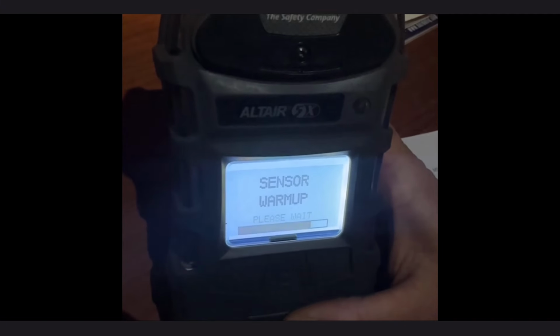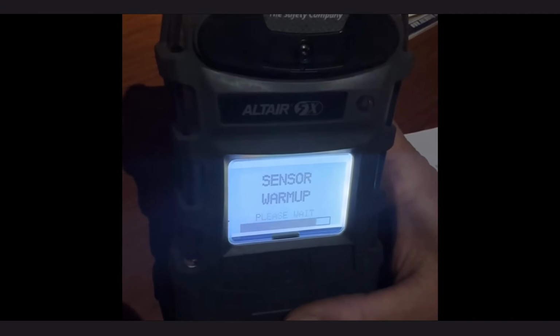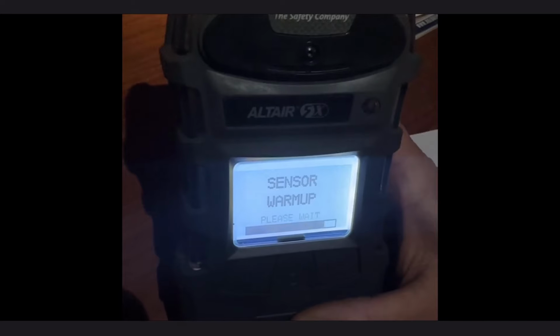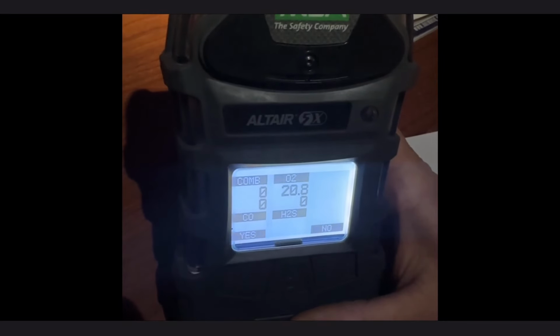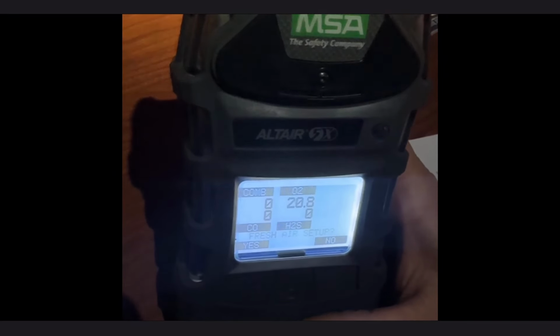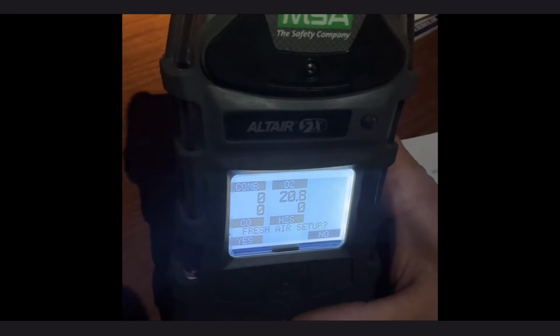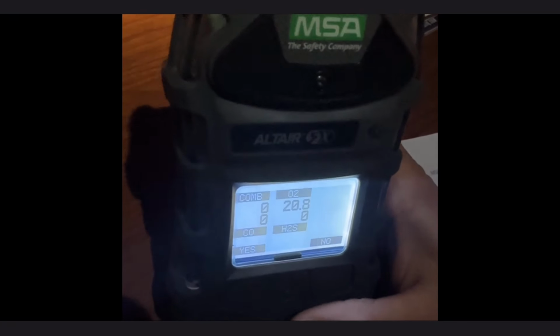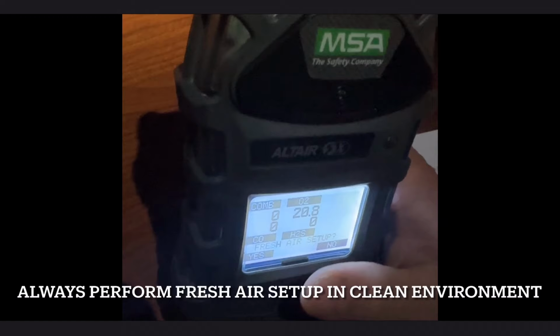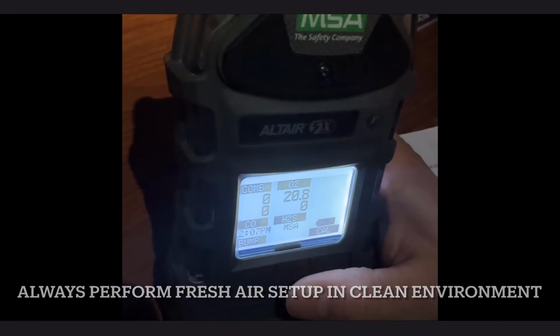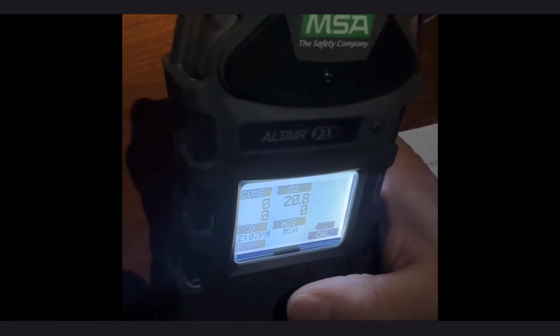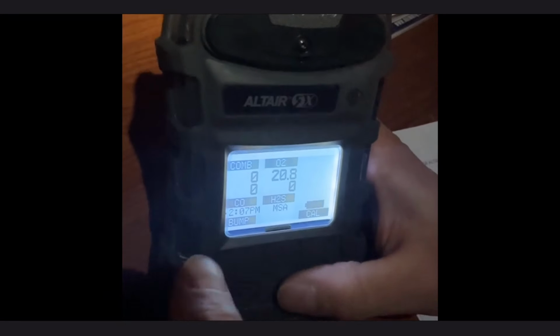Here's that warm up of that LEL sensor and all the other sensors. And then it's ready. It'll prompt you if you want a fresh air setup. All fresh air setup is making sure you're in a clean environment. If I were to hit yes, it's just running exactly what it says, fresh air over the sensors to clear out whatever residual they have on it.